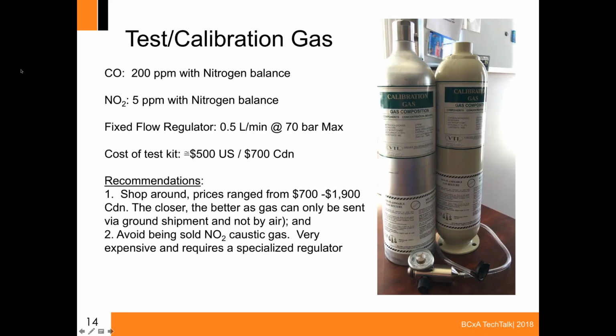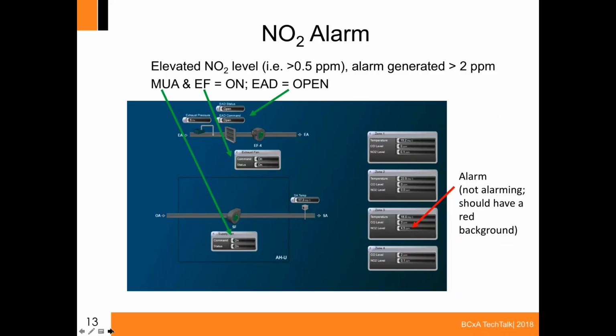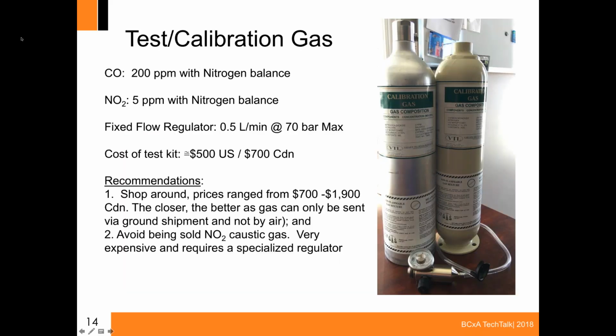So the test calibration gas kit, this is something that you can purchase through any of the local gas supply companies that have this type of gas. What you would want to get is a kit that contains a CO gas canister with 200 parts per million and a nitrogen balance, and the nitrogen dioxide would be at 5 parts per million with a nitrogen balance. Stay away from caustic nitrogen dioxide because that increases your cost significantly. You need a fixed flow regulator as well at a specified amount like 0.5 liters per minute.